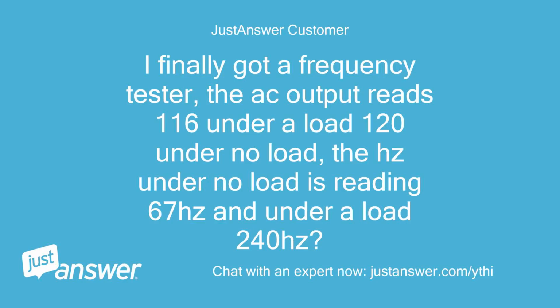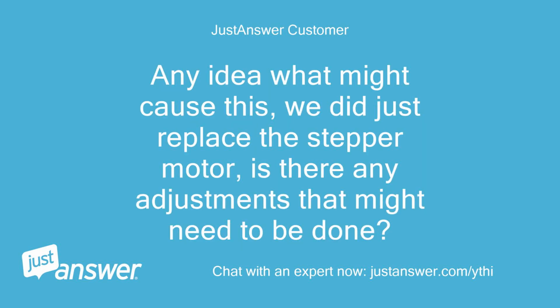I finally got a frequency tester. The AC output reads 116 under a load, 120 under no load. The Hz under no load is reading 67 Hz, and under a load 240 Hz. Any idea what might cause this? We did just replace the stepper motor. Is there any adjustments that might need to be done?